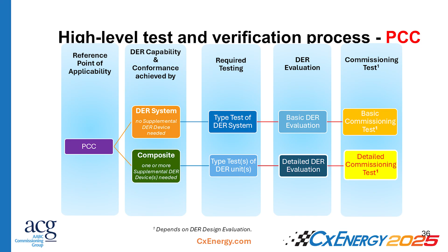But the point being here, if you remember, Mark had the point of interconnection, the POI, on the left of that one-line diagram. And that is what we call in the terminology of 1547 the PCC. So just think of the point of interconnection. It could be where the utility connects up to the facility. If it's a simple house, it's often the meter. Where the meter is located is that point of interconnection. Might be a disconnect switch, could be a variety of things, okay? So when you see PCC, that's what we're talking about, okay?